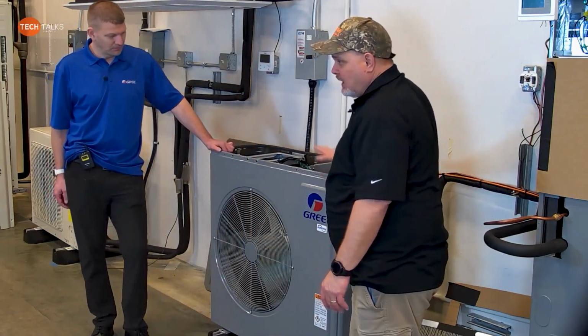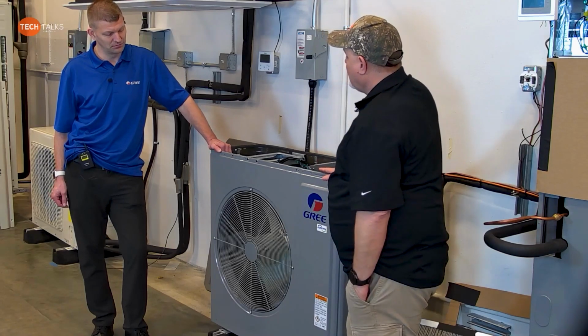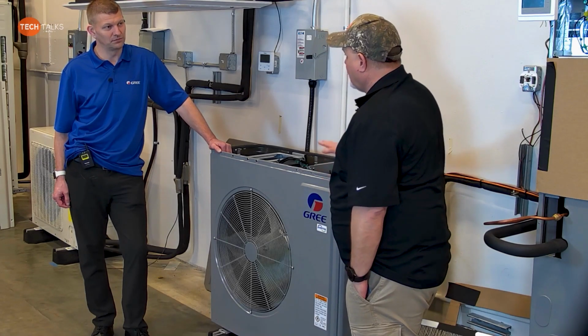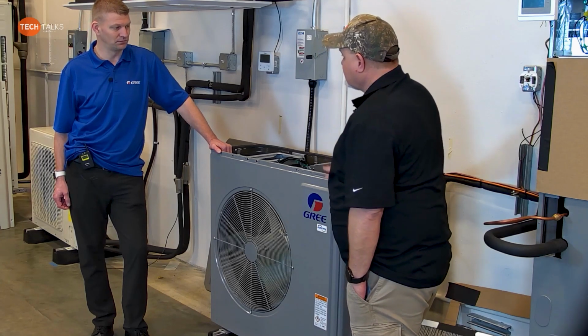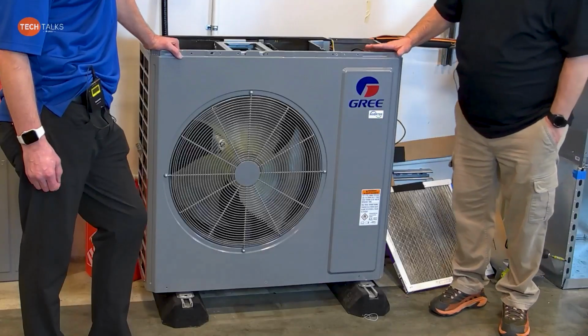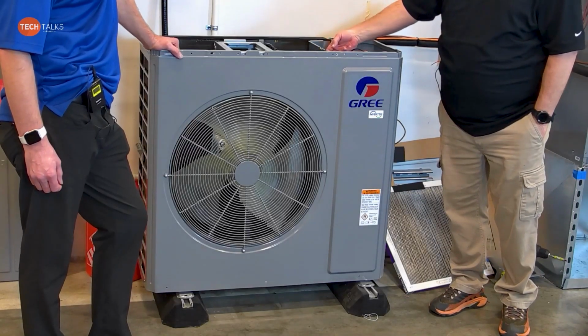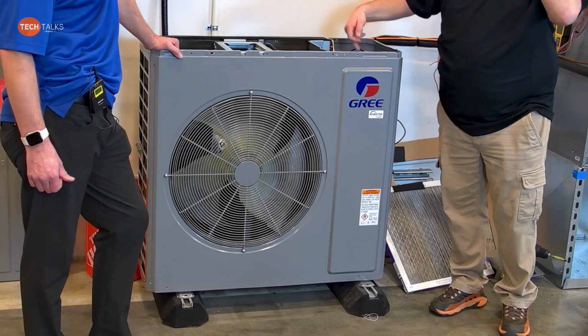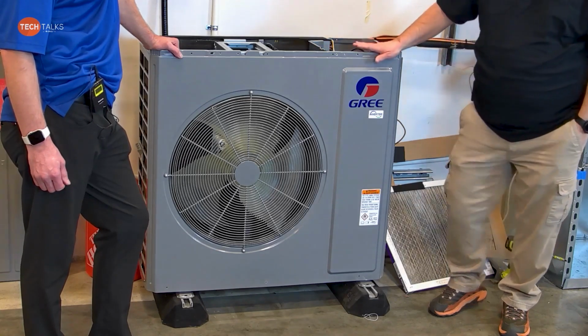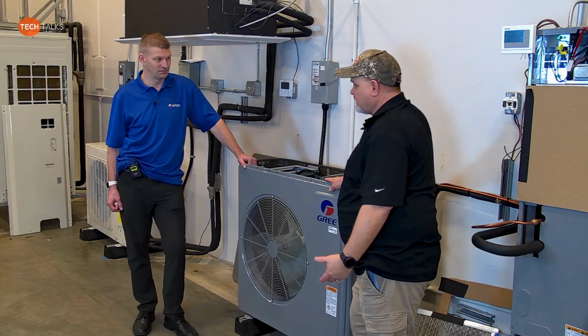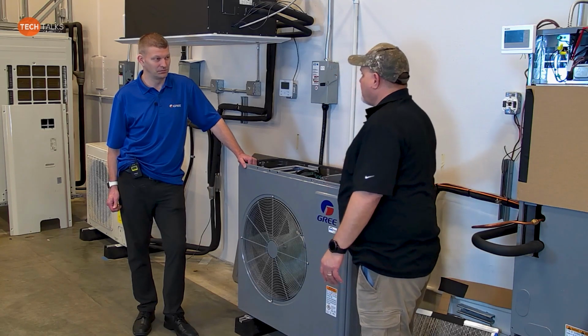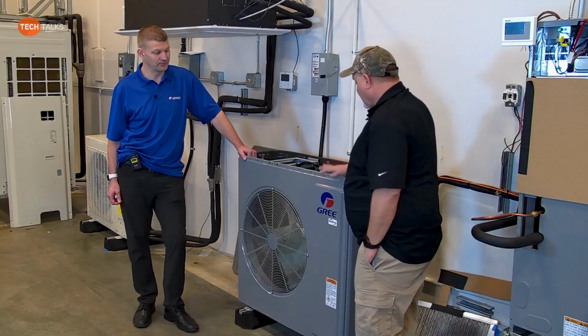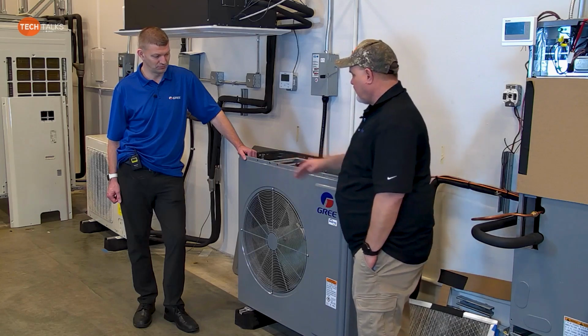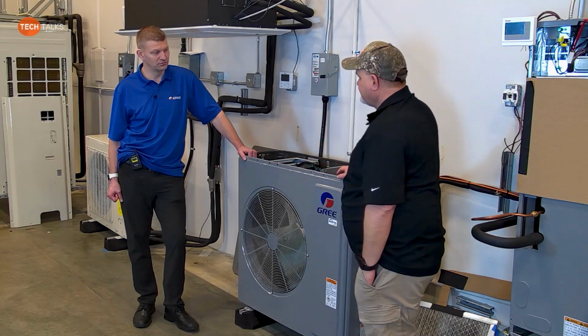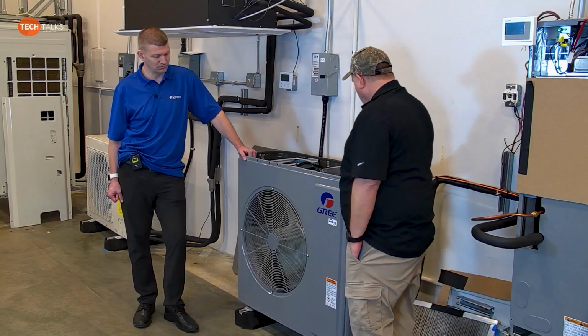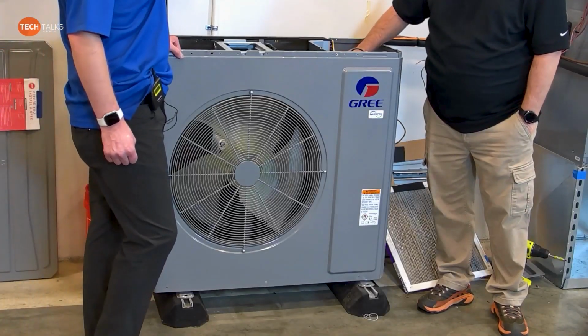In my opinion, compared to the 2 and 3 ton previous 410A Flex, this is much easier to get into and service and work on. Because the other one had, remember, the separate drive board back here, the communication board, the filter board, then the main board in the front. I've gotten phone calls from guys, and I'm like, okay, did you check the drive board? What drive board? They didn't even know the boards were in there because they never pulled the side panel off. So I kind of like this. It's a lot easier. Once they pull this panel off and this panel off, you can easily see every board in there.